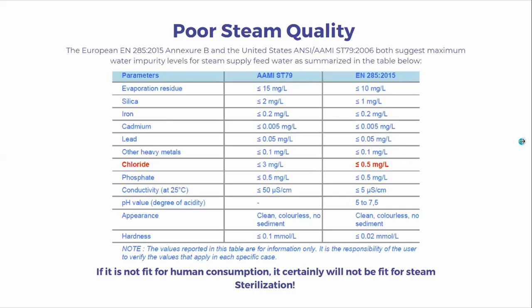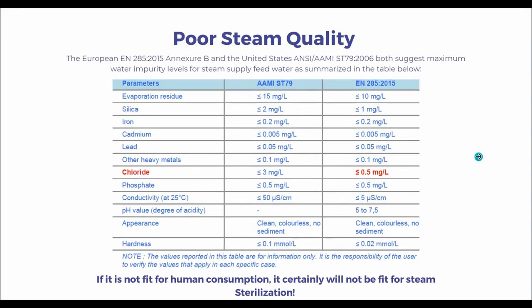Right, and then if we look at the table that will follow, we will see the European EN285 2015 and the United States both suggest maximum water impurity levels for steam supply feed water, as summarized in the table. If it's not fit for human consumption, it certainly will not be fit for steam sterilization. Thank you, Shane. The last bit, it's just a closing word.